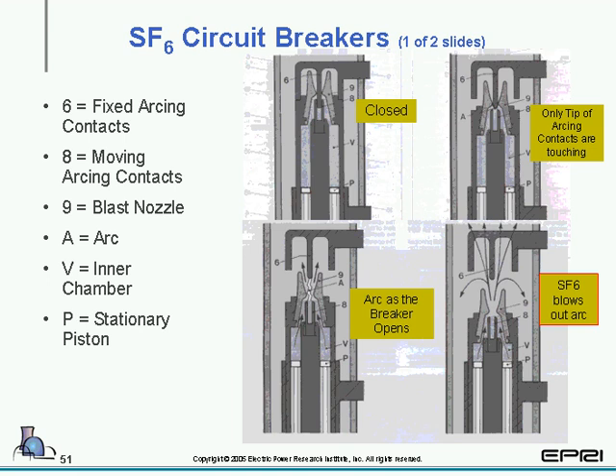The arc as the breaker opens, you see that as a white line, and it's actually marked A, the arc. The SF6 gas, at that point in time, you'll see arrows. And these arrows are the actual SF6 gas being pushed past the moving contact structure as it moves down. And then, of course, the last one in the lower right is the SF6 blows out the arc.